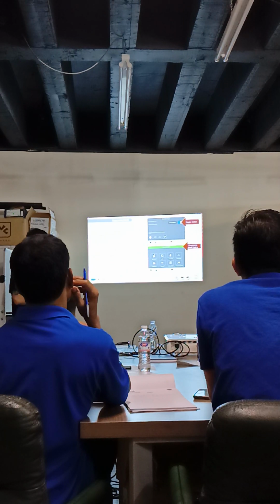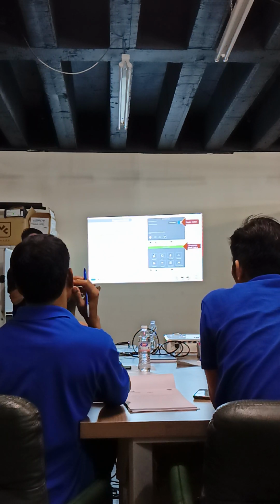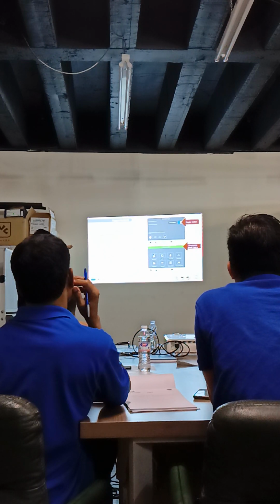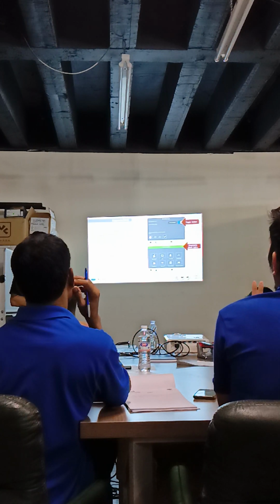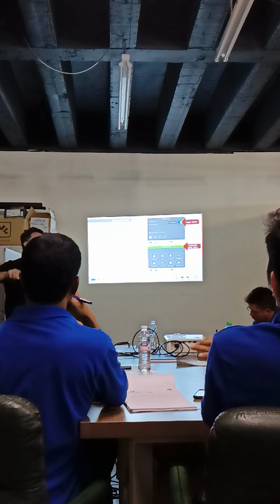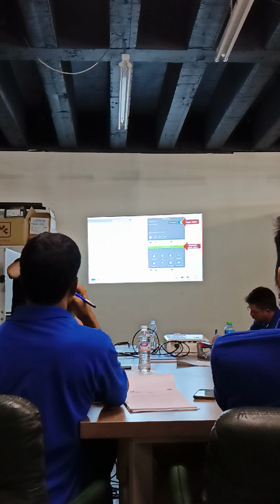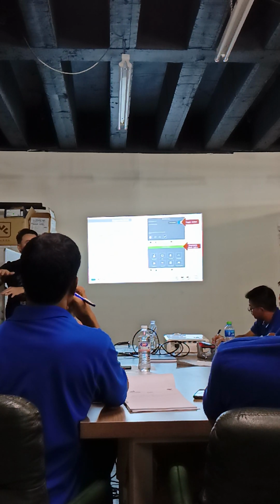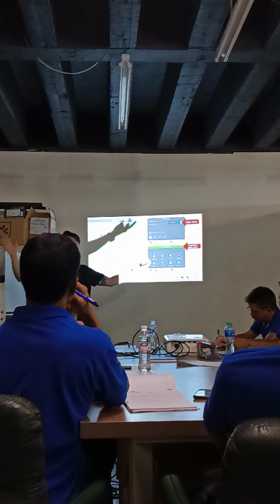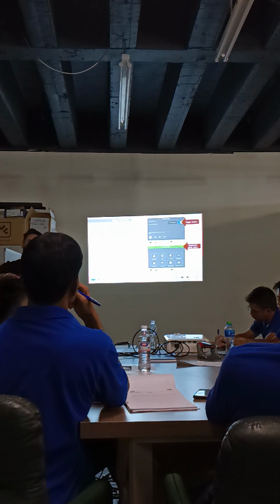All you do is go here, switch the relay on, and wait. If the temperature starts to rise, everything's working. If it doesn't start to rise, well, I've switched my relay on, so now I have to take the panel off and test if my relay is passing voltage. Yes - so it's not my relay. Now I have to test to see what's causing that problem. But it's pointing you in the right direction of where to look, instead of just looking everywhere - it's telling you where to look on the grill.